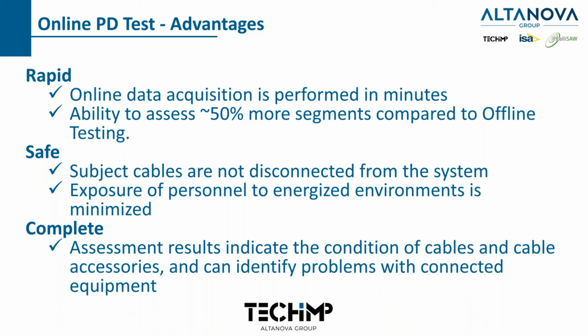And it's complete. What I mean by complete is that we're not just testing the cables. Because the cables are connected to assets, whether it's switchgear, transformers, motors, whatever, we're able to pick up partial discharge not just from the cable, but from the asset it's connected to as well. So the report will include not just the cable, but all the assets in the cable system. Another advantage of online testing.